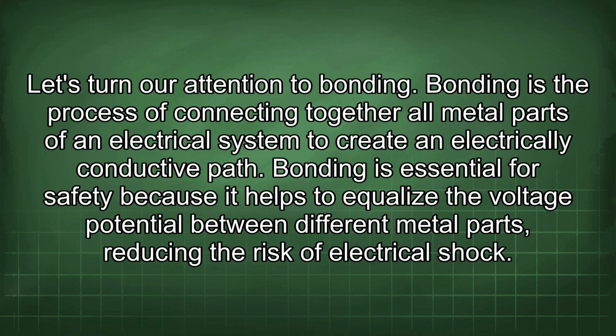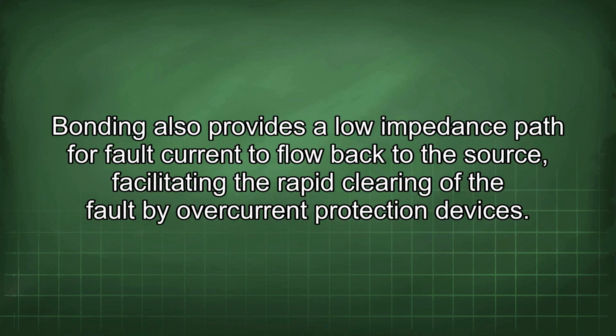Let's turn our attention to bonding. Bonding is the process of connecting together all metal parts of an electrical system to create an electrically conductive path. Bonding is essential for safety because it helps to equalize the voltage potential between different metal parts, reducing the risk of electrical shock. Bonding also provides a low impedance path for fault current to flow back to the source, facilitating the rapid clearing of the fault by overcurrent protection devices.